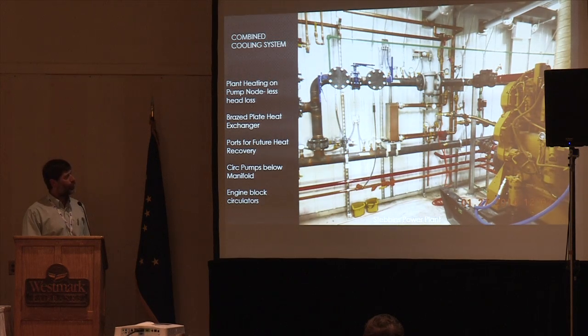Now what we're doing to pull off heat for our power plants is we're putting in what we call a pump node. So you're actually pulling liquid off of one part of the manifold, pumping it through this heat exchanger, and putting it back in. That way the engine is just seeing this larger loop, and it's not really seeing the force of having to push fluid also through a heat exchanger.